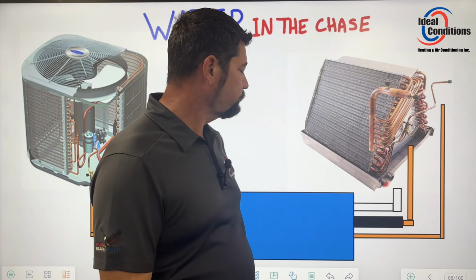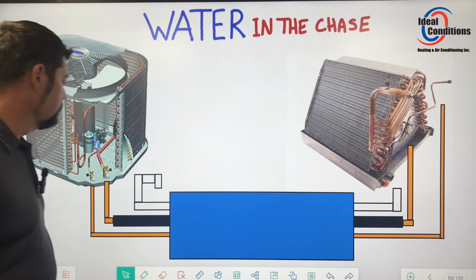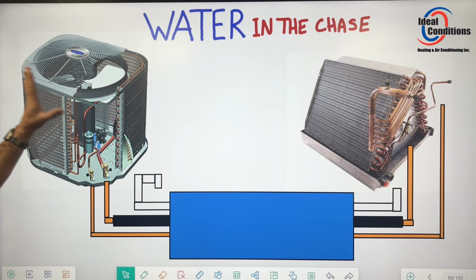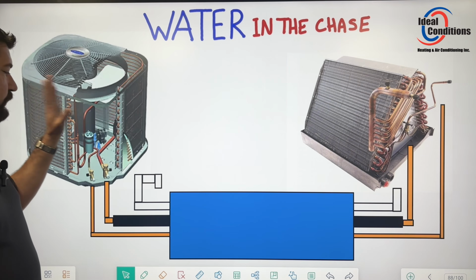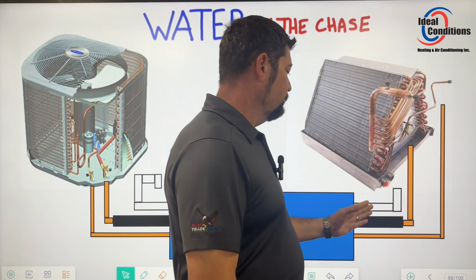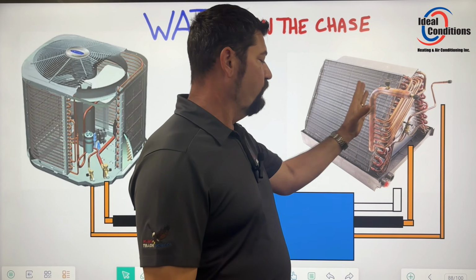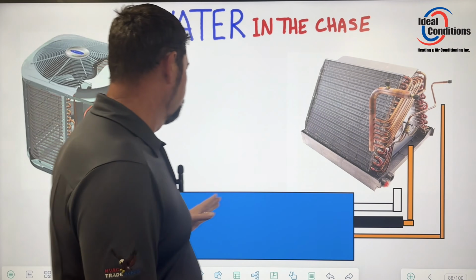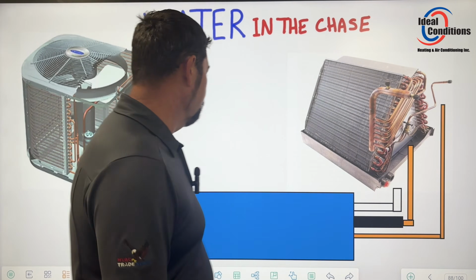But at the end of the day, if you're losing compressors and your superheat is changing, and you don't have that consistency, then the only thing that would make sense is to start checking the journey that your copper is going from point A to point B.